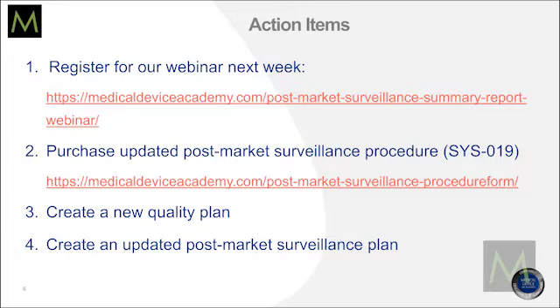If you didn't do any of these things and you'd prefer to get a major nonconformity or have your certificate and license suspended, that's an option. That's what's going to happen to a lot of companies because they aren't even aware that Canada changed the regs. The MDSAP auditors are going to come in, say you didn't address any of these changes, and issue a major nonconformity. If it's a repeat nonconformity — because you also missed the European MDR changes — they may suspend your certificate.